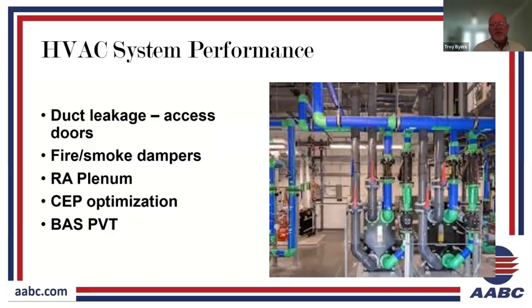So one of the very important elements, if we didn't touch on it in the air handler slide, is a system static pressure profile. We talked about a static pressure profile of the air handling unit itself, but I don't think we touched on the system static pressure profile, meaning going out into the duct system. You could measure duct static at a quarter, halfway, and three-quarters down a given VAV system, for instance. Or if you have vertical duct going down a shaft, you could measure at different points in the distribution of that duct. But what that's going to identify is any high pressure losses, and a shut fire damper would definitely give you a high pressure drop from one side of that damper to the other. So it's going to help you troubleshoot and understand any issue that has occurred in this existing building, due to whatever reason that might take place.